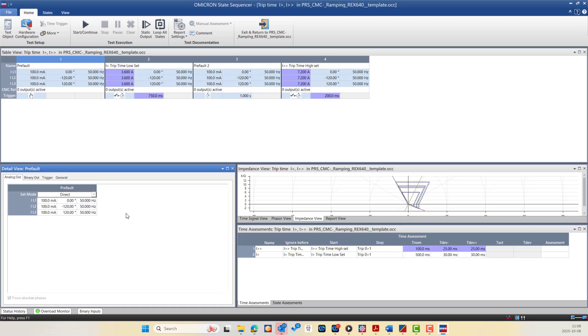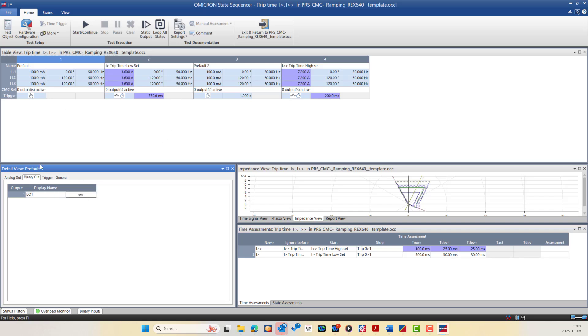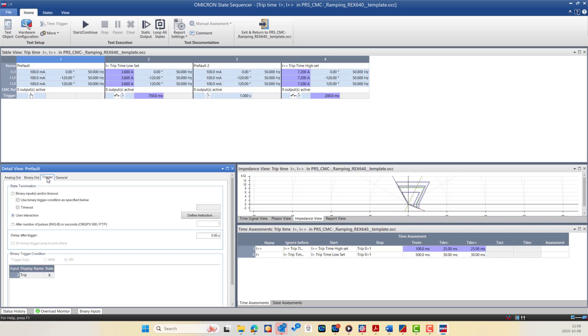For example, if you are simulating a phase-to-phase fault, you have to make sure that the phase angle between the faulty phases is 180 degrees. We also have the Binary Output tab, where you can define which binary outputs are active during the state by simply clicking close or open per state.